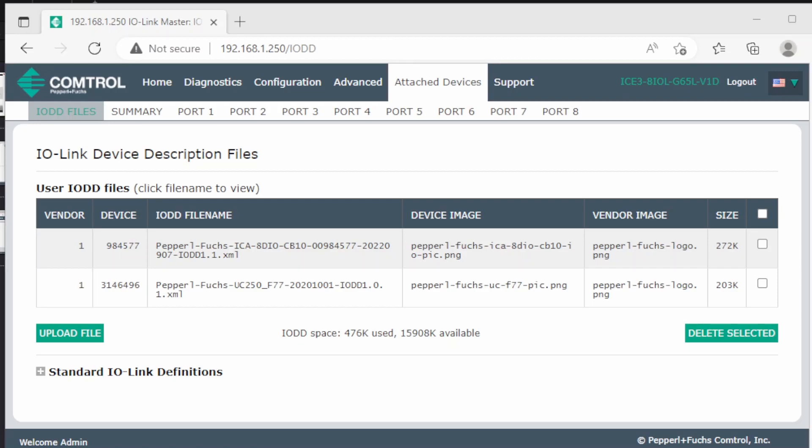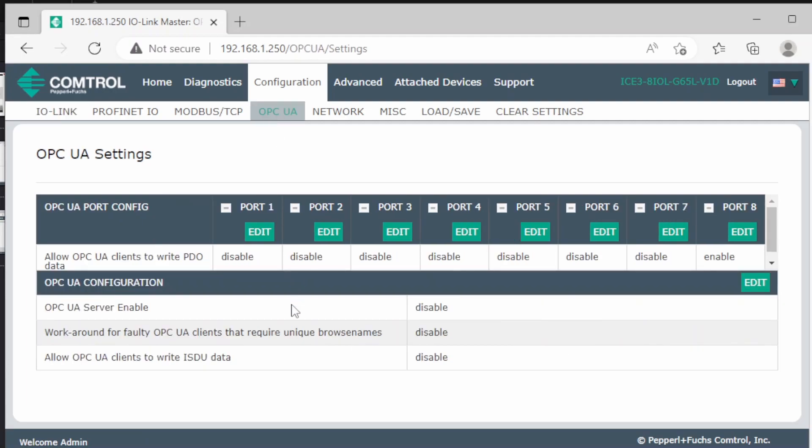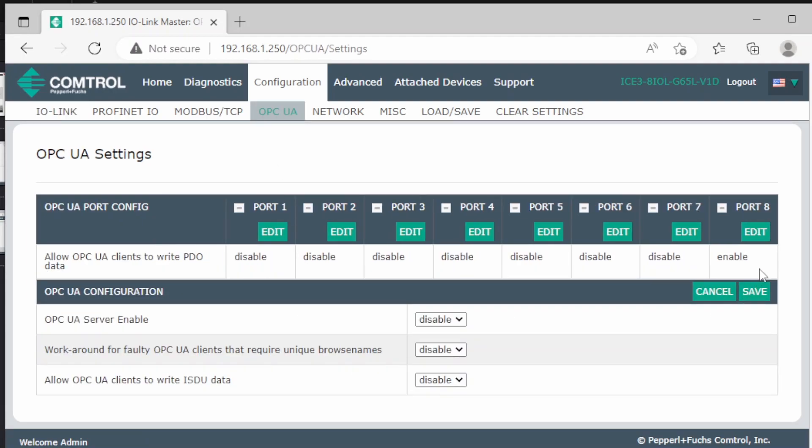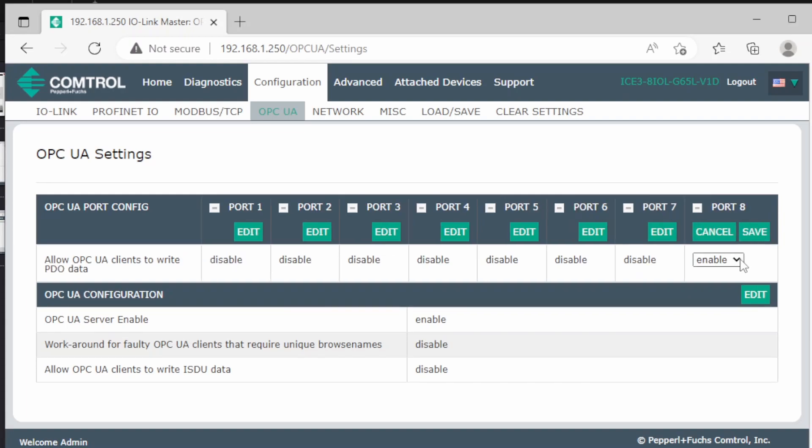Now we can move on to activating the OPC UA server. We can go into the configuration part here, open the OPC UA tab, and we can edit here. Then we press enable on the server and press save. We also need to make sure that this port 8 has writing enabled, because we are going to write to one of the 8 outputs later. So you press edit and change it like this.